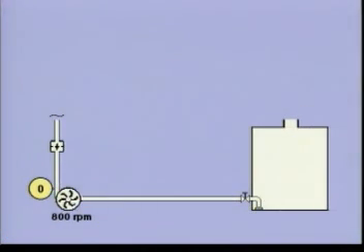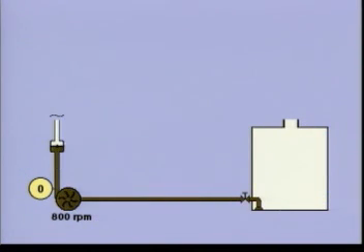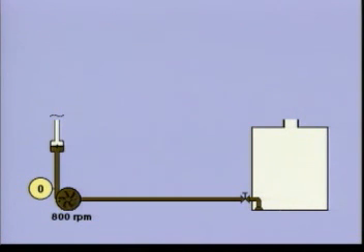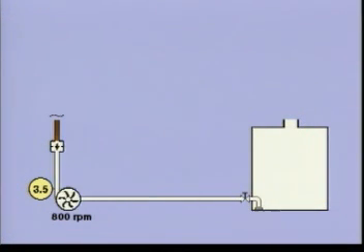In the end, there will not be enough oil to feed the pumps continuously. When a pump loses suction, close the discharge valve. The pressure will rise again, so open the discharge valve. The pressure will fall again, and you have to repeat the same procedure over and over again until the tank is empty. By skillfully manoeuvring the speed of the pumps and the discharge valves, you will be able to manually prime out almost all cargo from the tanks.